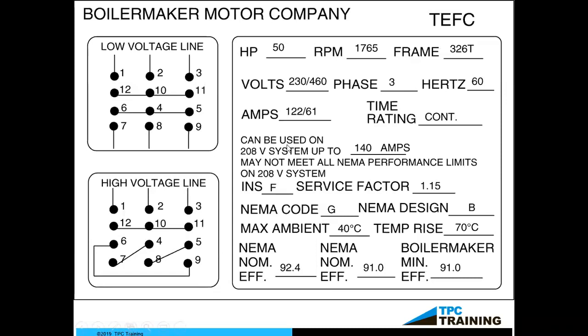The next little section tells us that it can be used on 208 volts, and if it does, of course, our voltage goes down, so our current is going to go up to about 140 amps, and we might not have the same horsepower. So it may not meet all of the National Electrical Manufacturers Association performance limits if we do go to that lower voltage, but we should understand that definitely it is going to be real close, extremely close.